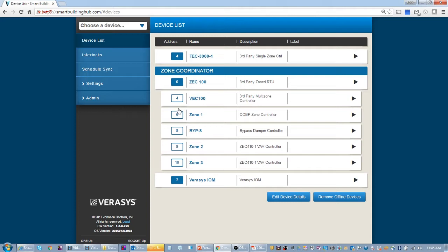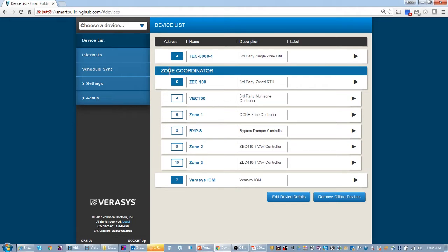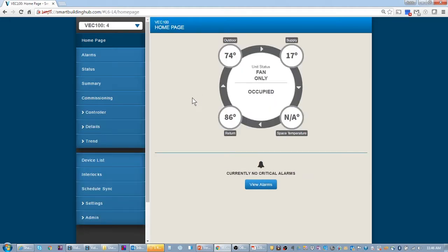Those are the devices that wire here. If it's a smart equipment rooftop unit, if it's VAV or changeover bypass, it must wire to the zone bus. Otherwise it could wire if it's a single constant volume or a constant volume unit, it could wire to the system bus.